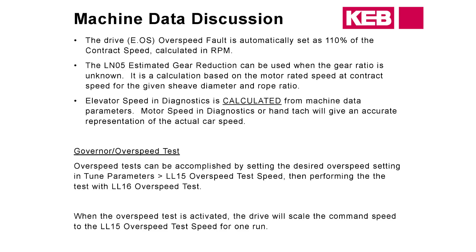Overspeed is calculated at 110% of the contract speed, so make sure US06 is set correctly. Sometimes you may have to adjust the gain settings if you're getting an overspeed while rolling over into contract speed from the XL portion of the profile. If you're getting it at the start of the run right away, it's most likely due to something on the encoder side.